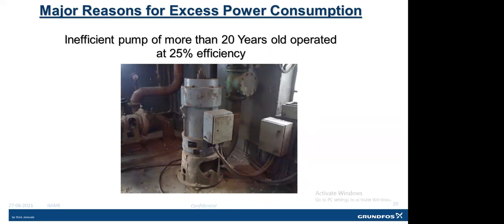So always check whether any technological advancement is available for this application, this pump, or any equipment, not only for pumps but for boilers, chillers, and cooling towers as well. For boilers, many technology upgrades have happened, such as installing a condensing economizer. For chillers, there are now chillers that come with variable speed, which directly reduces the specific power consumption of the chiller at lower loads. So always check for technological advancement, whether we can save energy by using the latest technology.